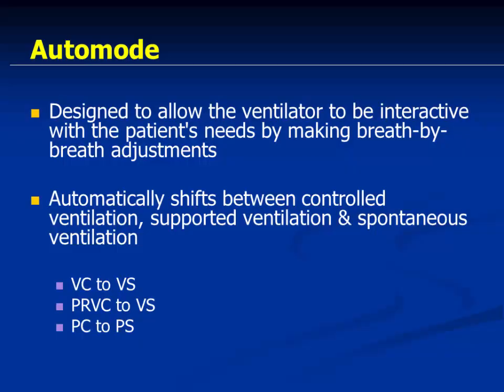Coming to another mode, Auto mode. Auto mode was present in Siemens ventilators before the name changed to Maquet. I don't know whether you people have used it or not. It was a beautiful mode. It was introduced in the 900 model. It was designed to allow the ventilator to be interactive with the patient's need by making breath-by-breath adjustments. It automatically shifts between controlled ventilation, supported ventilation and spontaneous ventilation. So it was a true auto mode.